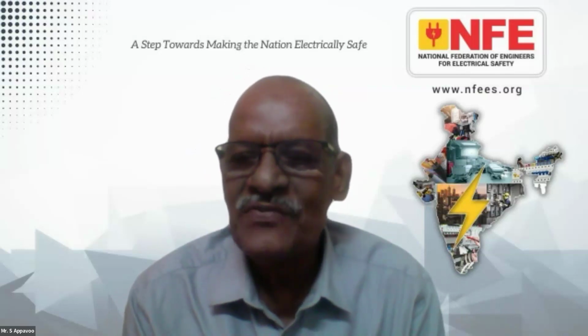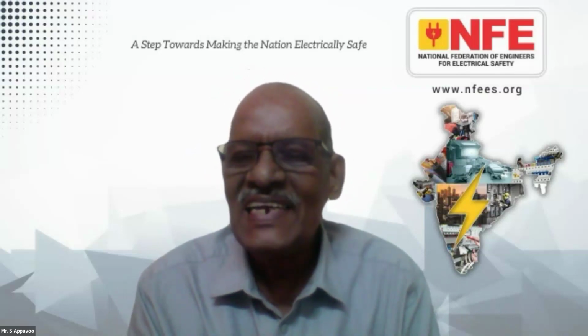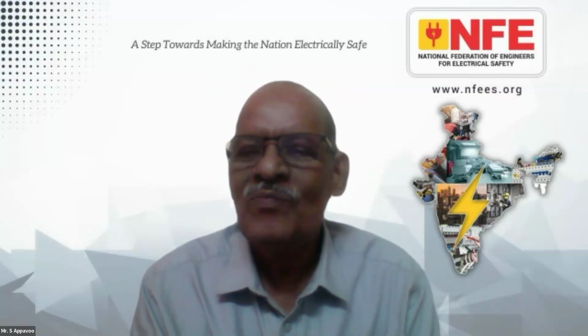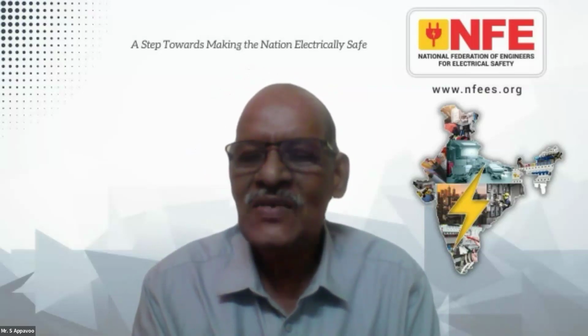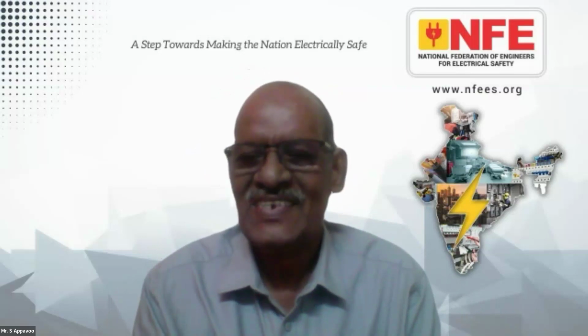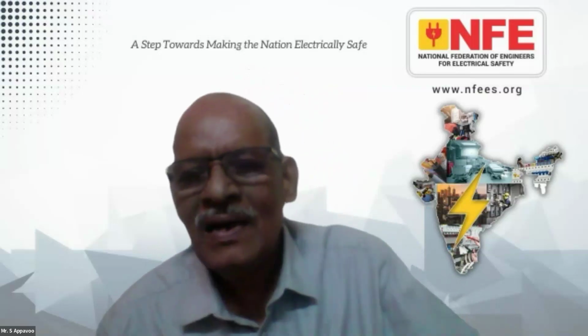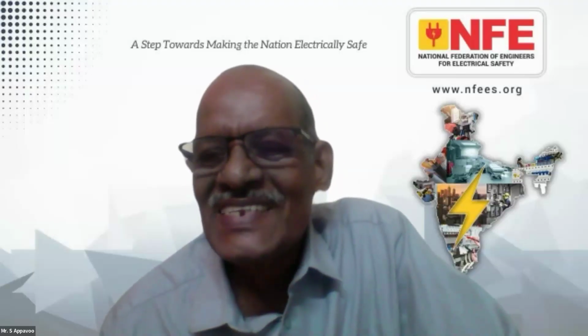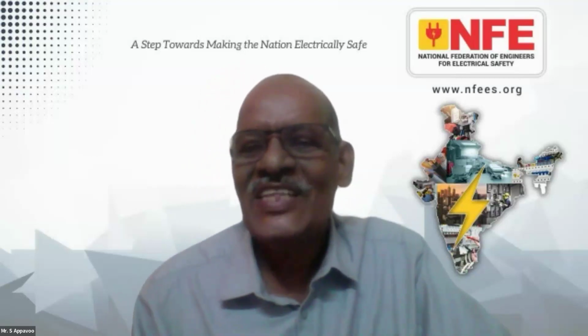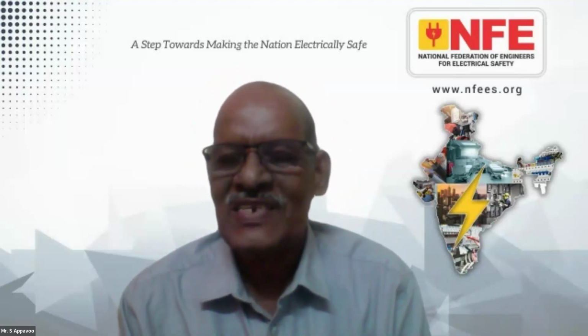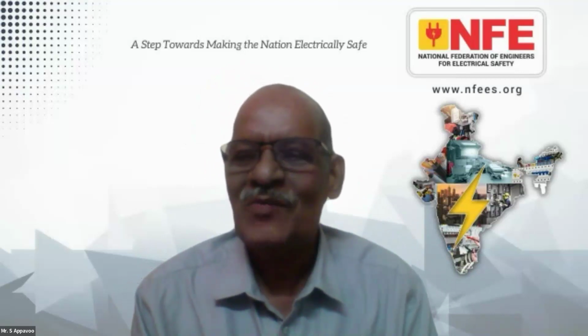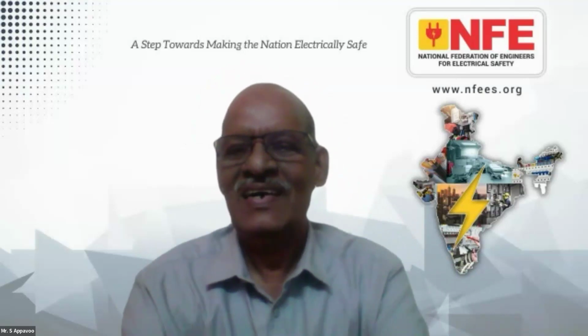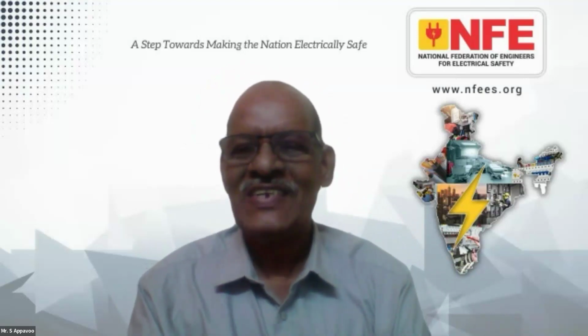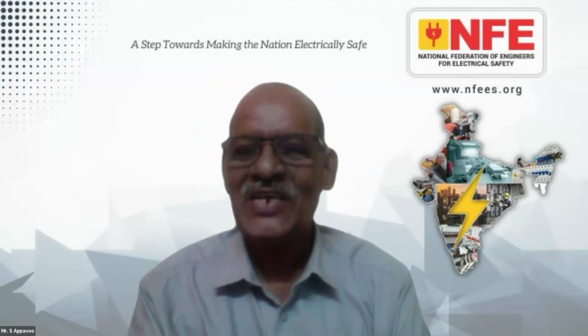Once an equipment is affected, you can symptomatically presume that some waveform distortion has taken place. Simple. It's a waveform distortion which affects the sensitive device first. And it will always follow the least resistive path. So the vulnerable things are on the least resistive path. Transformer, of course, can bear it because of its high capacity, but sensitive equipment will become the victim in most cases.